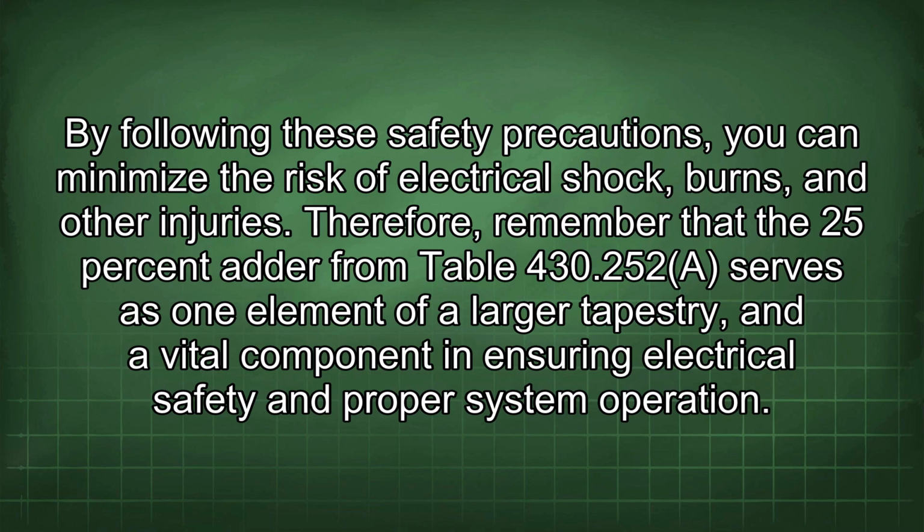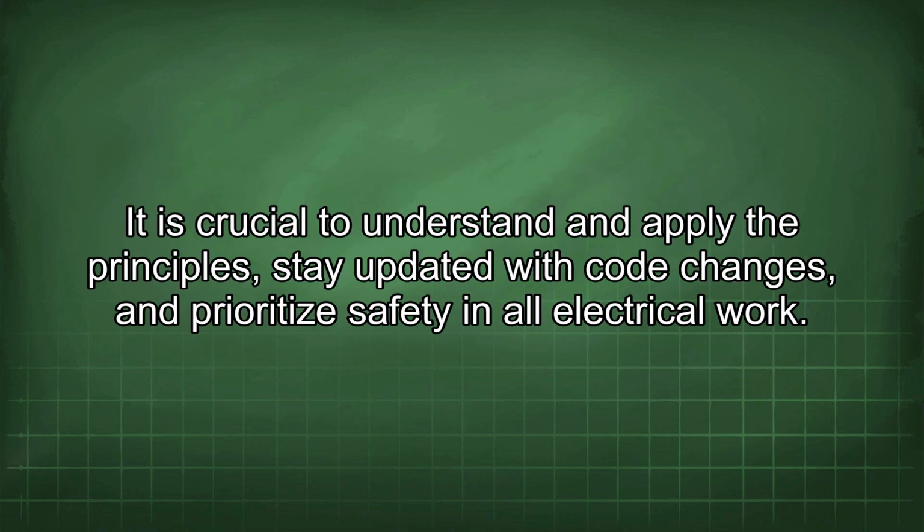Therefore, remember that the 25% adder from Table 430.252 serves as one element of a larger tapestry and a vital component in ensuring electrical safety and proper system operation. It is crucial to understand and apply the principles, stay updated with code changes, and prioritize safety in all electrical work.